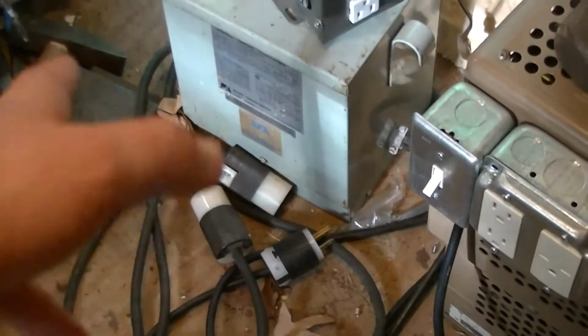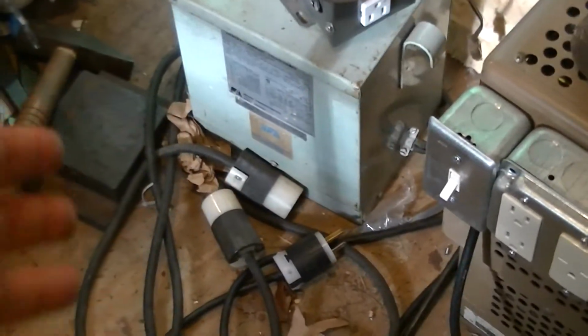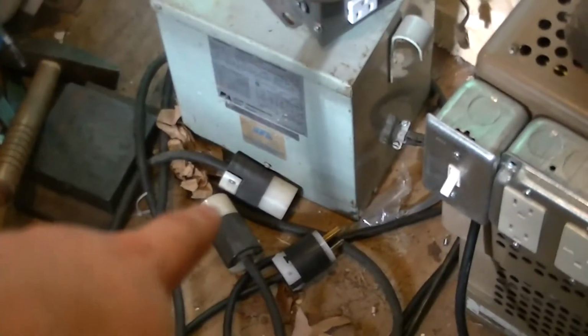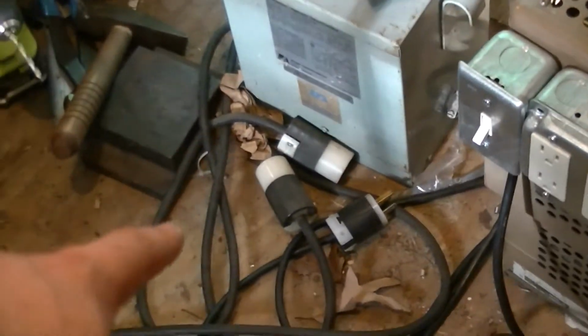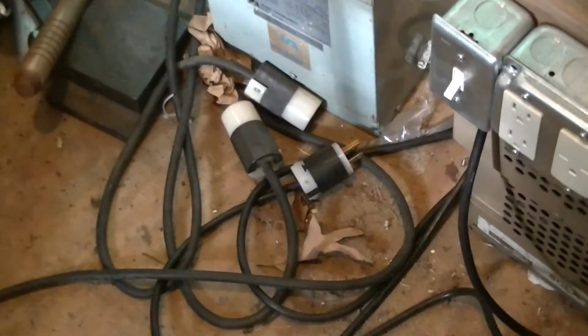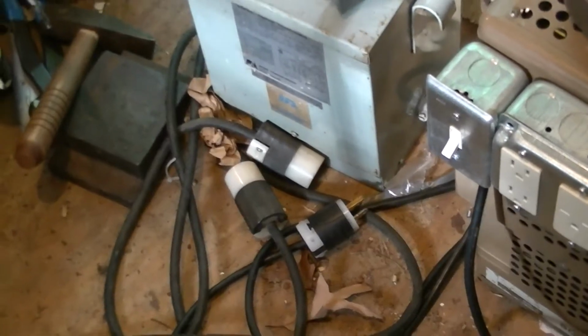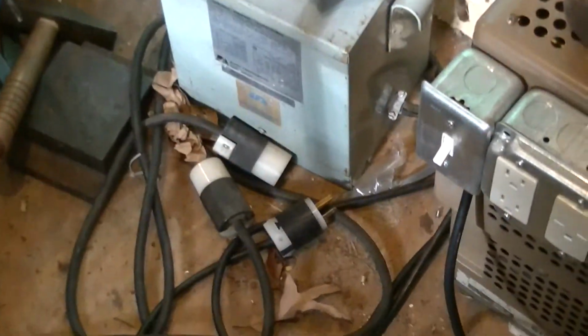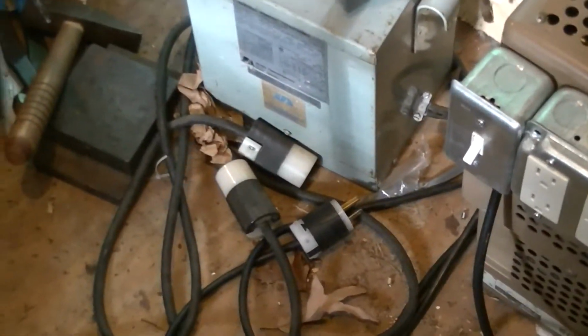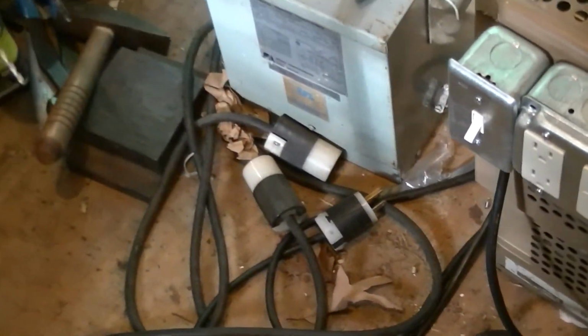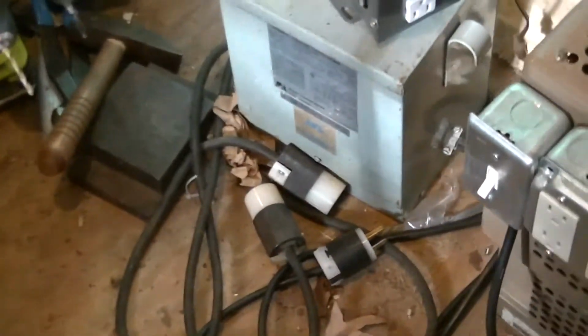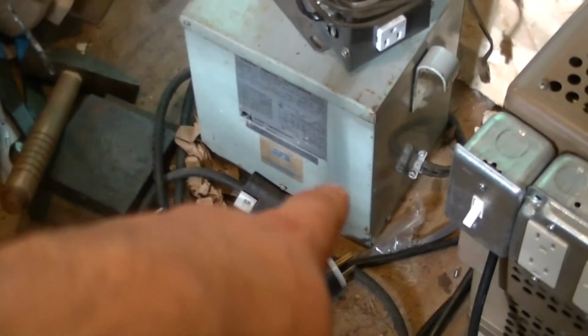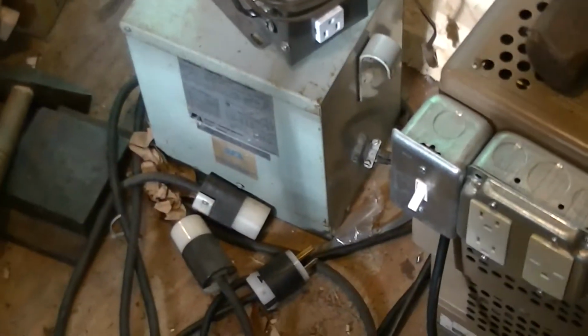So you feed in 120 volts, and right now it gets 228 volts out. What I am going to do is modify the wiring so that one of the receptacles is 228 volts out, one of the receptacles is 240 volts out, and I might add a third, which is 252 volts out. That's the full use of the windings, as well as replacing the power cord with a 12 gauge one so that I can use it much closer to its rating.